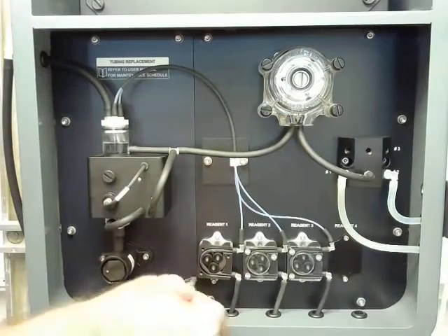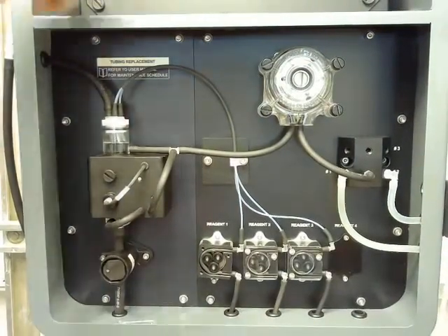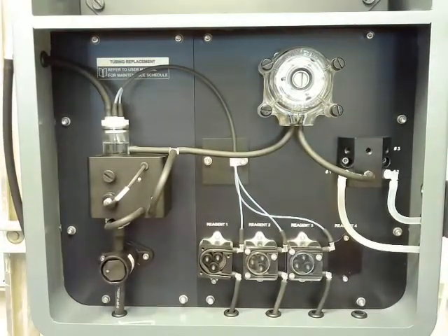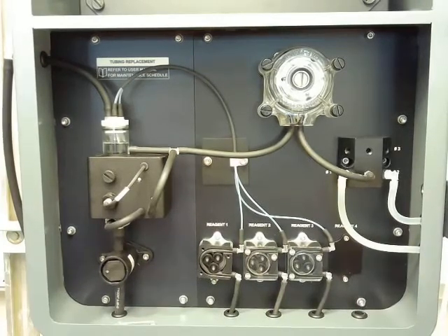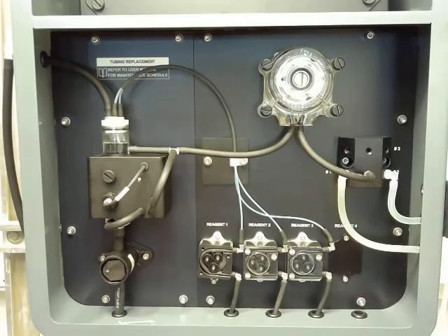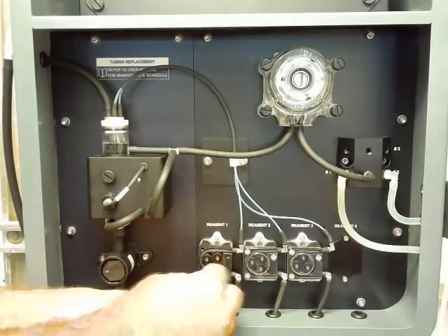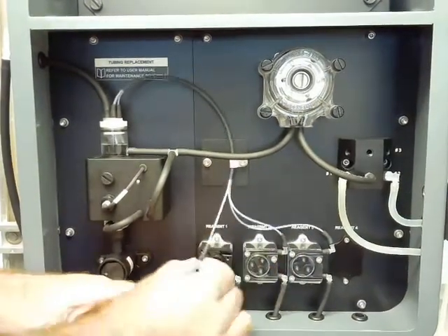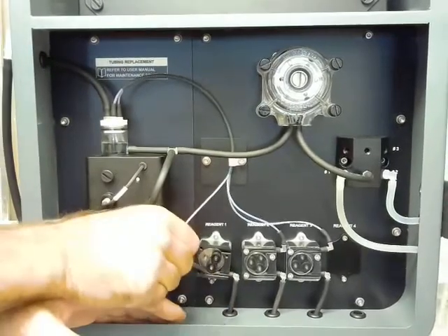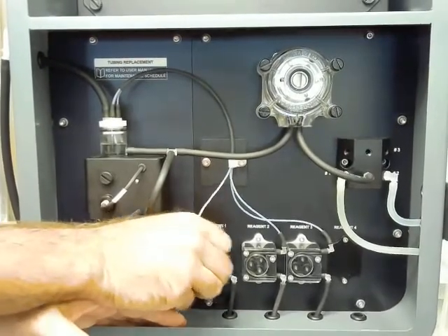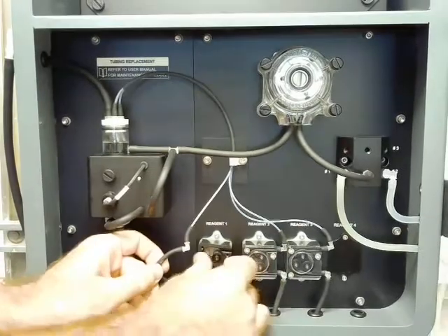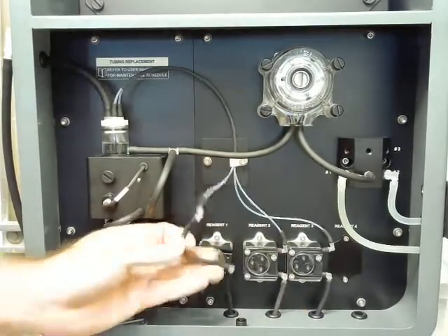And once we have this cover off, and you set that aside, it's a good idea to inspect for any leaks, any excessive dirt buildup. Or obviously, if we have moisture on the inside of the pump, we'll want to dry that out. And then we just need to look to see if it came from a leak or actual wear through of the tubing. But once we have the cover off, we can pull the tubing off, and what will probably happen is the rollers will come out with the tubing. That's okay because we need to get them out anyway too. So you can take them out and set them aside.